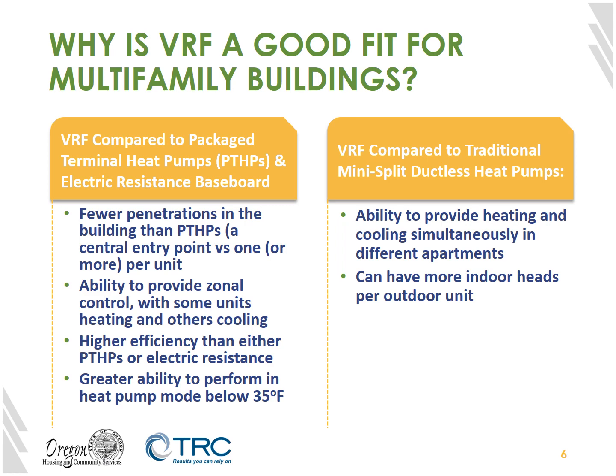It does provide the ability to do zonal control, with some units being heated and some units being cooled. This is truly where some of the special sauce with VRF systems comes into play. For tall buildings where you may need heating on the top floor and cooling on the bottom floor or vice versa, or buildings where the south side may need cooling and the north side may need heating on the same day at the same time, these VRF systems are really a nice approach to being able to deliver this. They also deliver higher efficiency than package terminal heat pumps and much higher efficiency than electric resistance heat. So if we're looking to maximize the energy efficiency, or in other words, lower the bills of the occupants the most, a VRF system can be the highest efficient system on the market to really do this for ourselves.